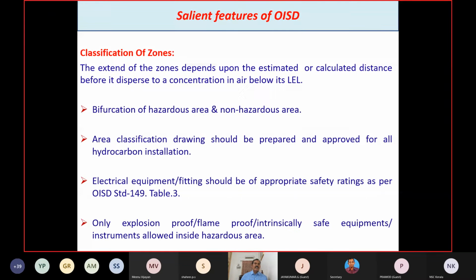Let's move on to the next slide. The extent of zones depends upon the estimated or calculated distance before it disperses to a concentration in air below its LEL. It will dissipate in the air immediately, so it depends on the distance only. Now, the bifurcation of hazardous area and non-hazardous area. As I have told already, all facilities will be bifurcated as hazardous area and non-hazardous area. Sometimes they may call it licensed area and non-licensed area.